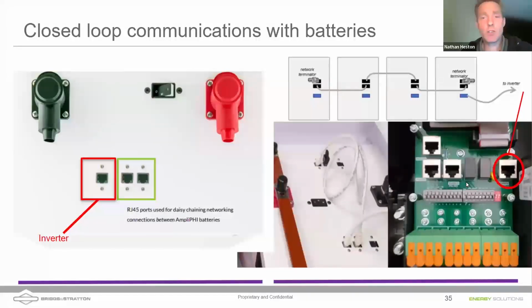Wiring the communication loops. So closed loop communications with batteries. We have 3 different ports on our batteries. So I'm showing on the left, this is a SimpliPhi battery. One of them is a device port. The other are for daisy chaining the closed loop communications on the batteries. So that one that looks a little bit different is actually labeled device on the battery. That one goes to the inverter, and you only need one battery wired from the device port to the inverter.